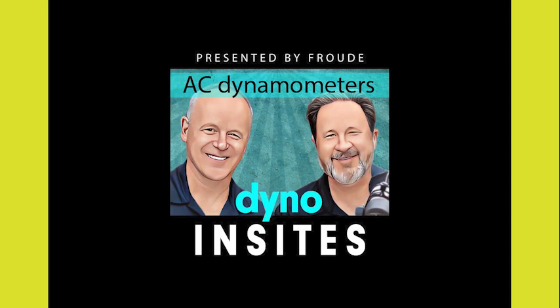So an electric motor typically is just something that spins, right? You put power to it, and it spins. It uses power to spin. But with a dynamometer situation, you're spinning, but you're also absorbing power from whatever's connected to it. That's the principle of a difference between an electric motor and an electric motor used in a dynamometer. As a dynamometer, you have to absorb the power. So it's effectively a generator that's resisting the prime mover, the test unit, and using the generating to slow the test unit down. Exactly. But with more sophisticated control?